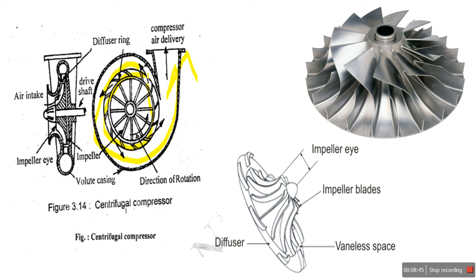Air flows outward through the impeller blades where both kinetic energy and pressure increase. As the air flows through the impeller blades, both velocity and pressure increase. The air then enters the diverging passage called the diffuser, where kinetic energy is converted into pressure energy, and is discharged into the volute casing. Finally, the high-pressure air escapes to the compressor delivery. In this compressor, air enters in the axial direction but leaves radially. These compressors are suitable for a pressure ratio of 4:1.